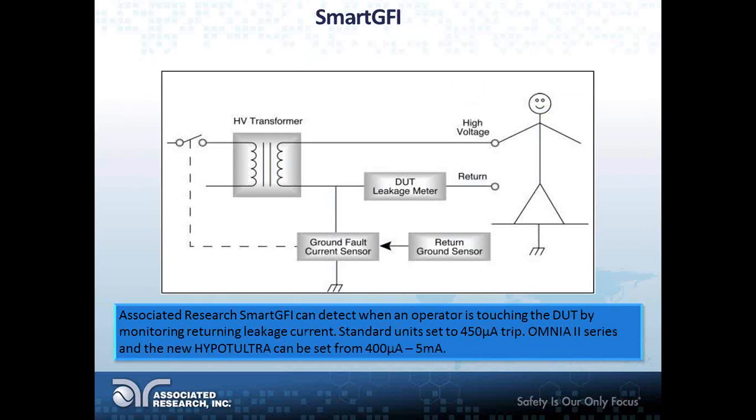So the way SmartGFI works is that it can detect when an operator is touching the device under test by monitoring the leakage current, as I said before.